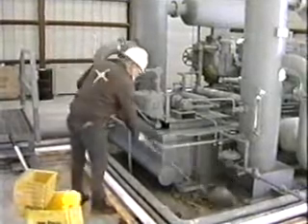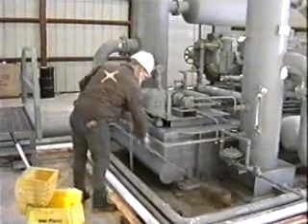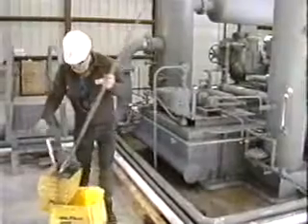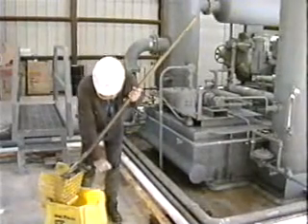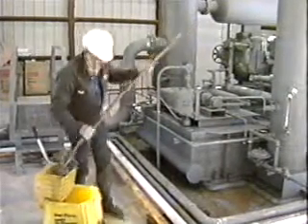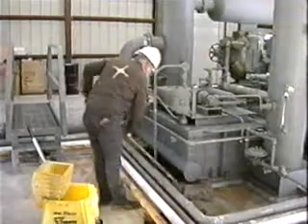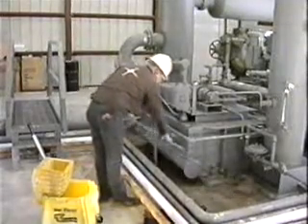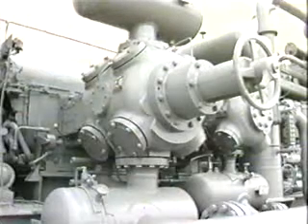Leaks are another indicator of a possible malfunction. The compressor or prime mover may have oil, gas, or water leaks. Gas leaks are potential safety hazards and should be scheduled for immediate repair or action taken to minimize the leak until maintenance can be done. All leaks should be thoroughly investigated to see if they indicate an operational problem or malfunction.